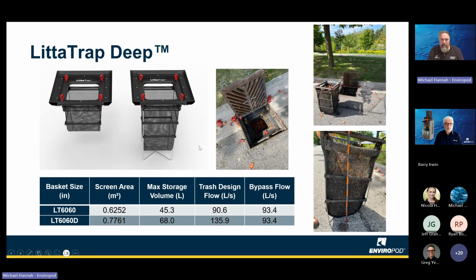Now, it can get very heavy. It is really Vactor only. I pulled this one out, but if you've met me, I'm a rather big guy. It wasn't that bad. I would have said it was about 20 kilos. I have these lifting hooks to help me lift out by hand. But yes, if you turned up and it looked like that unit in London, it's a Vactor clean. You should not try to lift that out by yourself. You won't be able to.